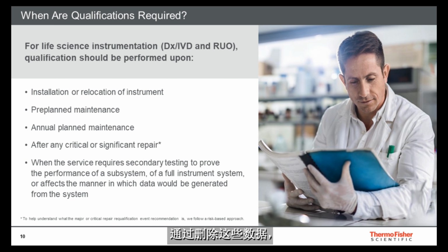By bracketing this data, it will considerably shorten or eliminate the risk of a long investigation of samples for an equipment failure that may have been caused during the PM. After the PM work has been completed, adjustments can be made to dial in the unit so it will operate at its peak performance without any risk. Once the unit is dialed in, post-testing is done so that the unit can be released for use. Now, please keep in mind that there are only a few situations that have warranted this as-found testing, but it is a viable option.